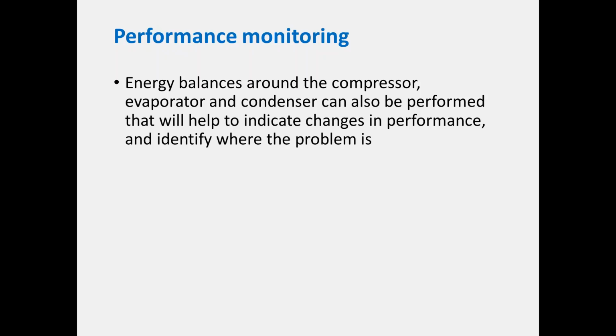Now, I know that often the refrigeration vapor compression cycle isn't set up with all those sensors in place, but as I said, with temperature at least, putting a cheap thermocouple on the outside will be a good indicator. It may be beneficial to install these other meters, particularly if you've got a problematic system.